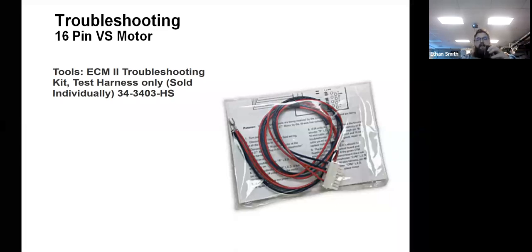This is my original TechMate that I bought a long time ago. And it has that 16-pin harness. It's got a few more wires in there because I can actually give it speed commands for cooling, fan on, heat mode, and various other fan speeds. And all I do is plug this in, make sure I've got 120 volts power, and then I feed it 24 volts power through these two jumpers off of my furnace board. So you can get tools like this. The modern TechMates are simply glorified go, no go harnesses. I don't recommend them as much.